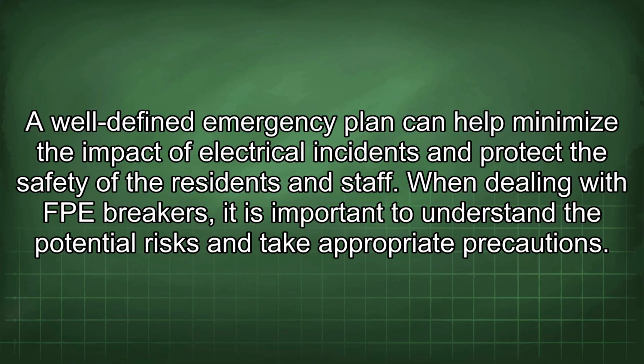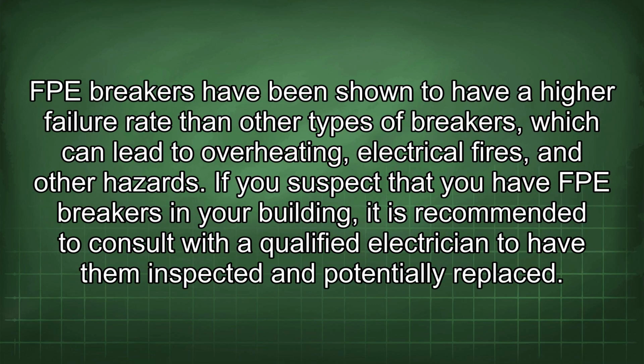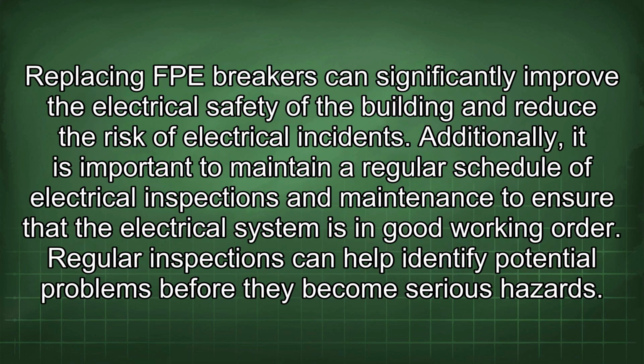When dealing with FPE breakers, it is important to understand the potential risks and take appropriate precautions. FPE breakers have been shown to have a higher failure rate than other types of breakers, which can lead to overheating, electrical fires, and other hazards. If you suspect that you have FPE breakers in your building, it is recommended to consult with a qualified electrician to have them inspected and potentially replaced. Replacing FPE breakers can significantly improve the electrical safety of the building and reduce the risk of electrical incidents.